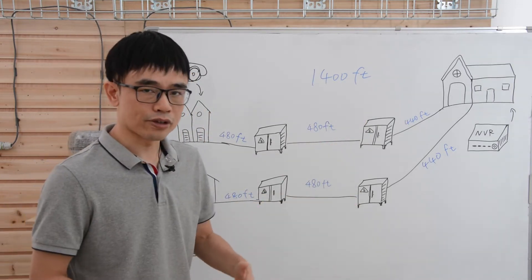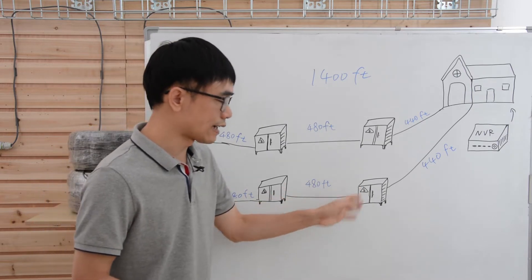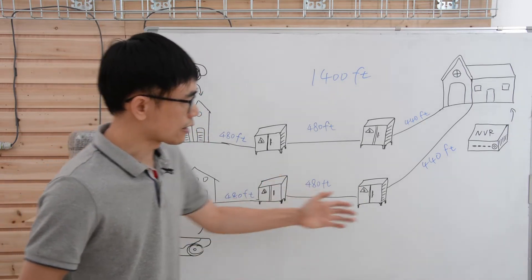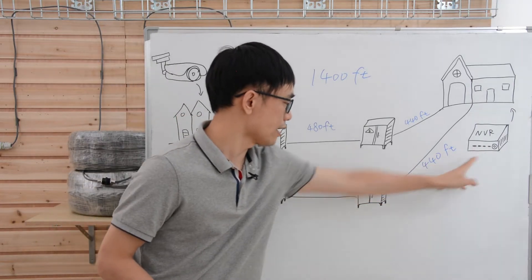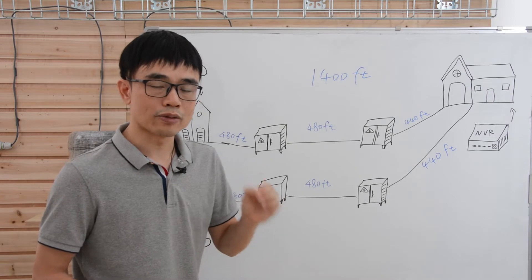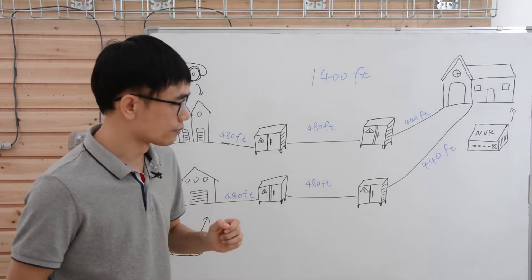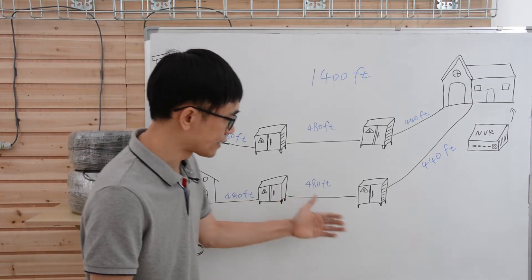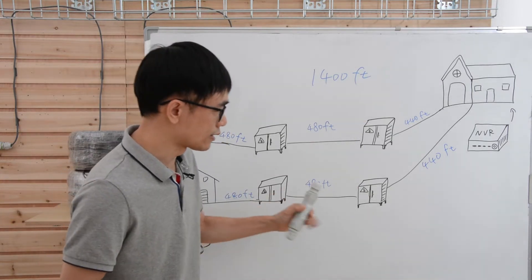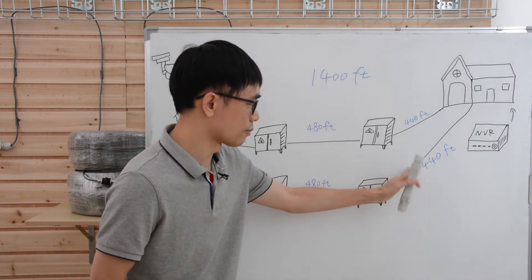Even if there are some issues in the future, he can reach the PoE extension equipment and diagnose the issue. But you can see there is about 440 feet from the NVR to the first enclosure. And we know the PoE only can reach about 328 feet. That means we cannot place the PoE extender in this enclosure. The PoE extender needs to be placed before, maybe somewhere here.